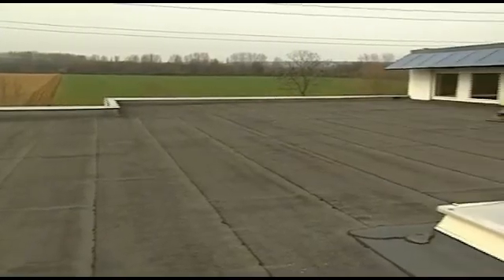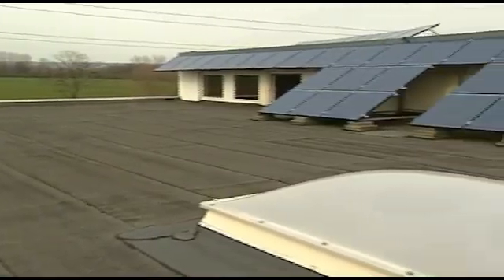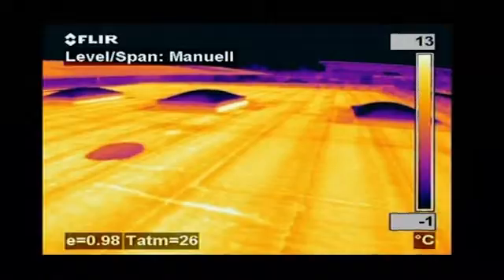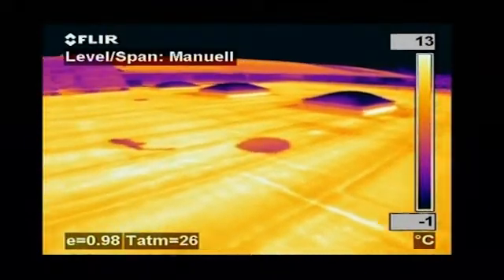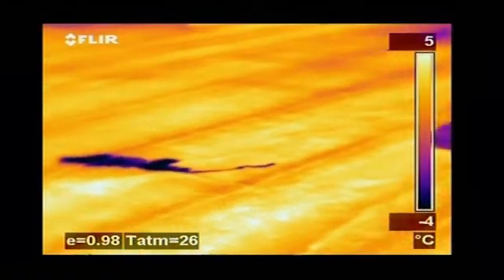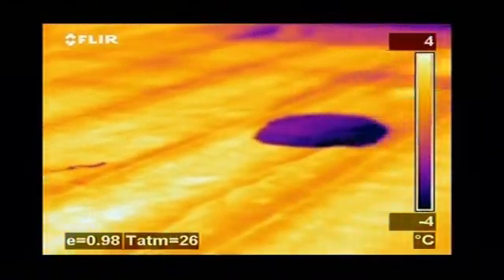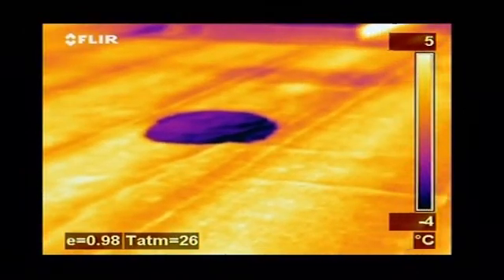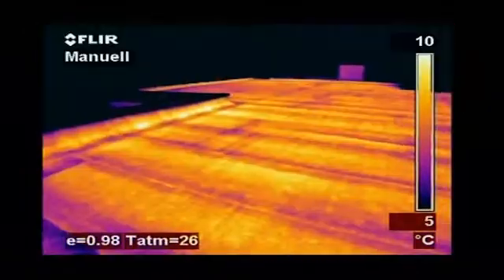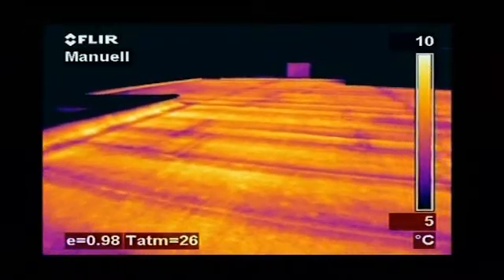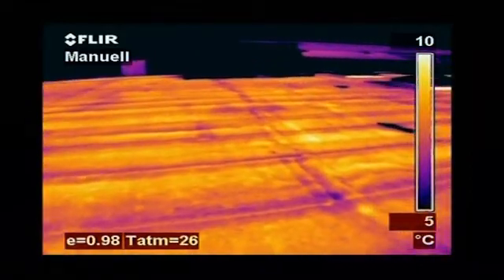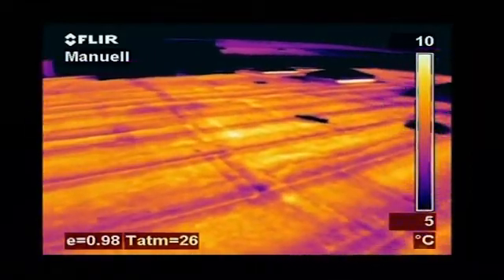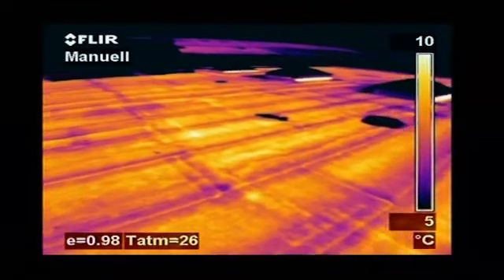Thermal imaging is also used to detect leaks in flat roofs. Water retains heat longer than the rest of the roofing material and can easily be detected with a thermal imaging camera very late in the evening or at night, after the rest of the roof has cooled down. Tremendous savings can be made by repairing wet areas rather than replacing the entire roof.